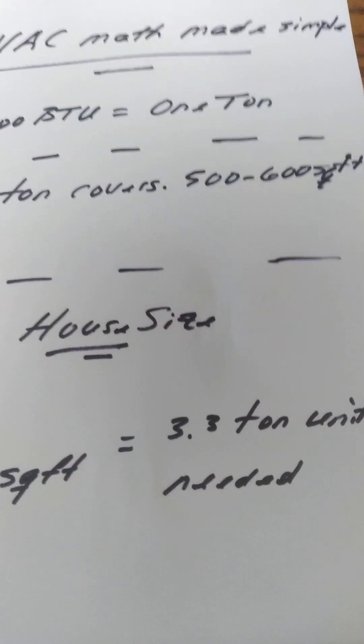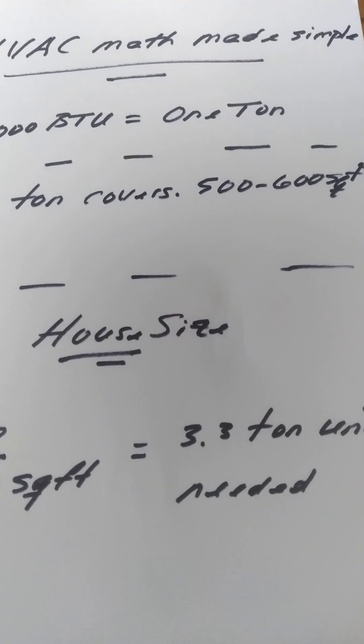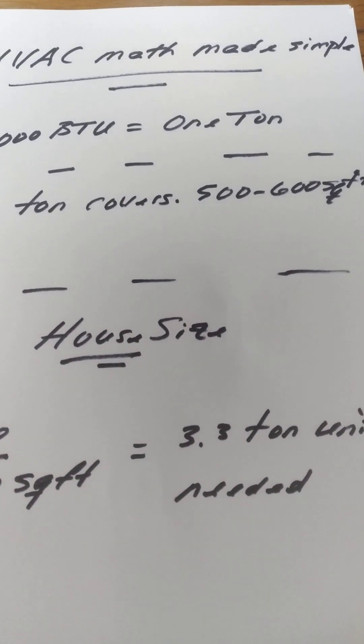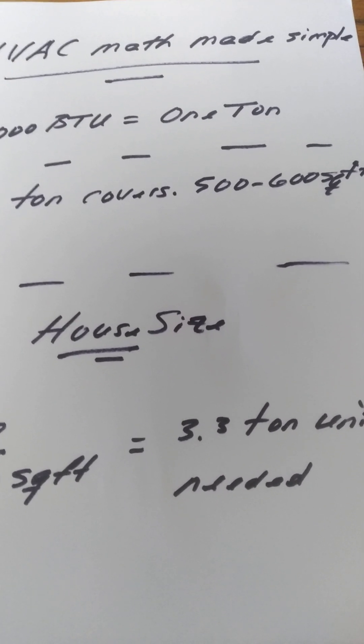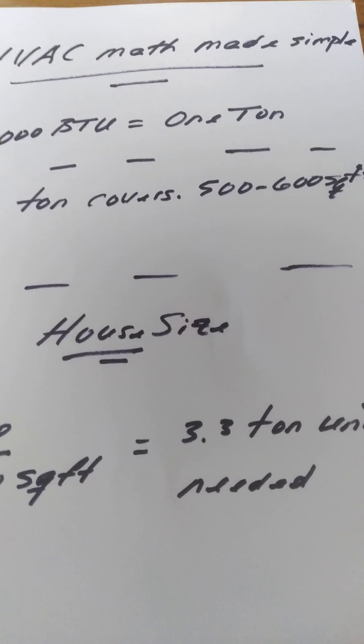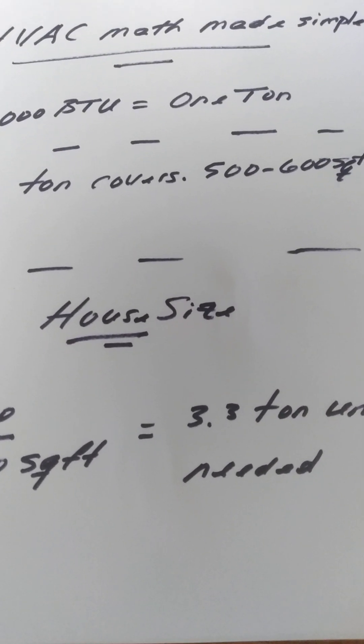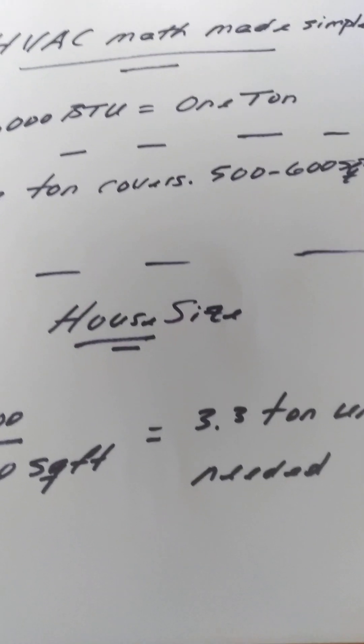You do not need to go much over a three and a half ton unit because if you do, then you will short cycle your compressor, your windows may freeze up. There are many different variables that are too much to cover in this video.